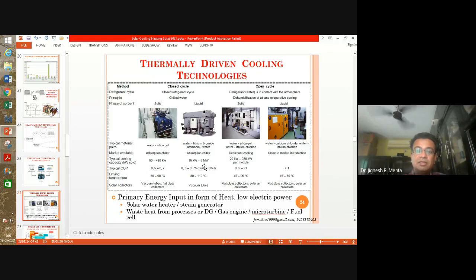And again, this is the absorption system. The most common one is water lithium bromide, another one is ammonia water absorption systems. And the typical cooling range is 15 kilowatt to 5 megawatt. Actually 15 kilowatt is mentioned, but normally such low capacity systems are hardly seen. And the typical COP, and this is for single effect, you can see 0.6 to 0.75. Adsorption has an even lower COP, and this is the COP based on the heat that you supply, right? So you can never expect COPs as high as those you get in vapor compression refrigeration systems.